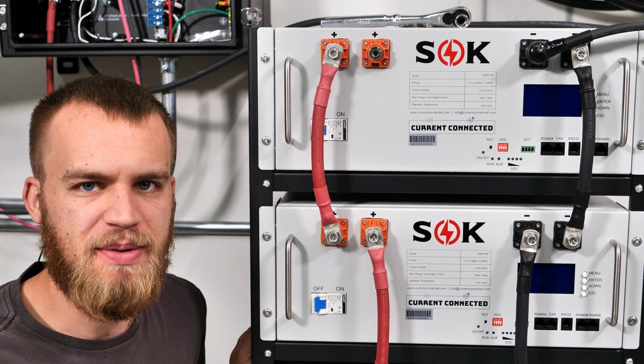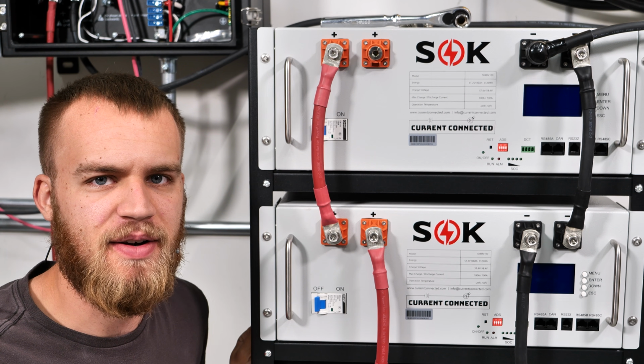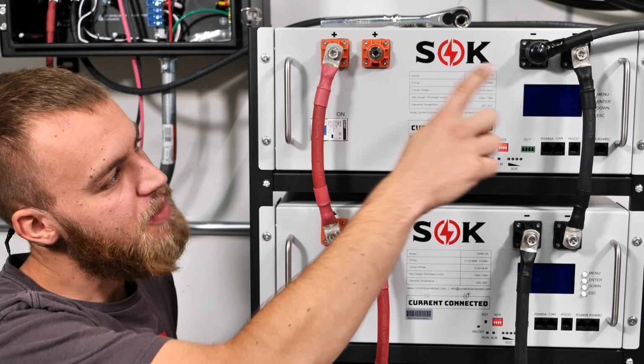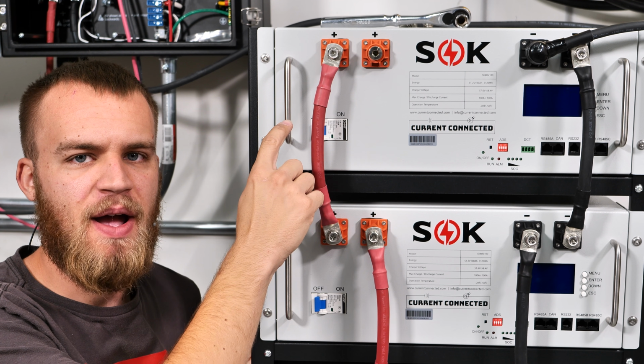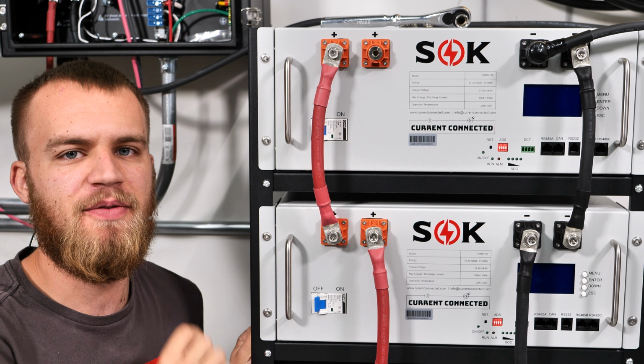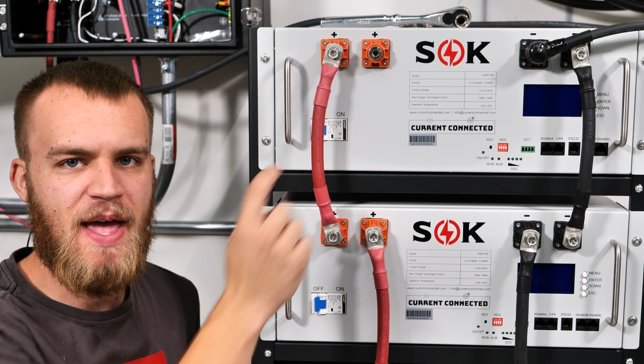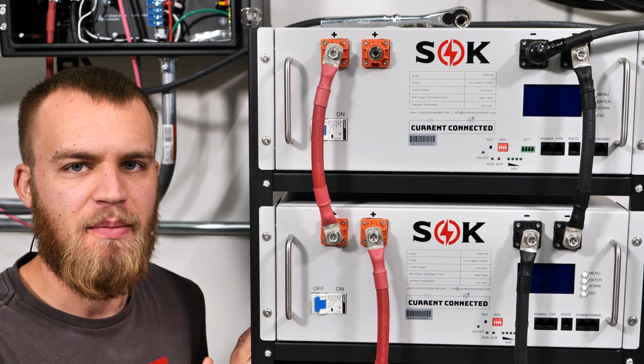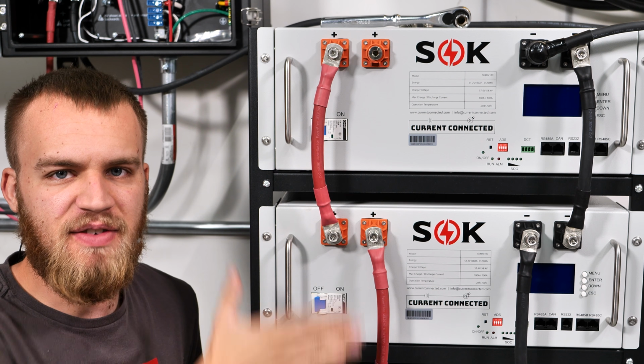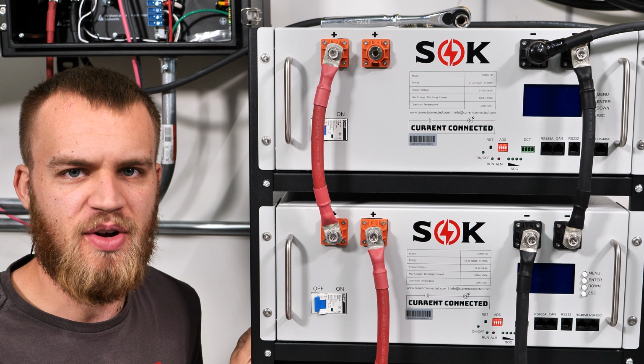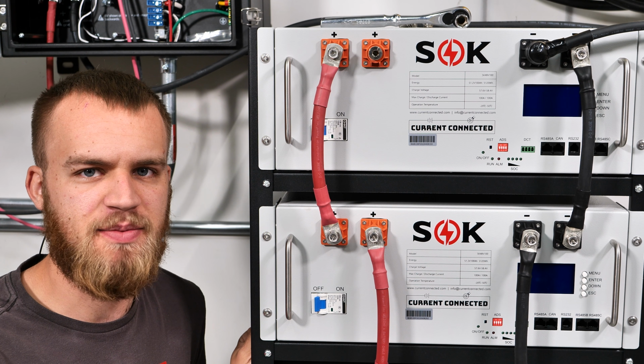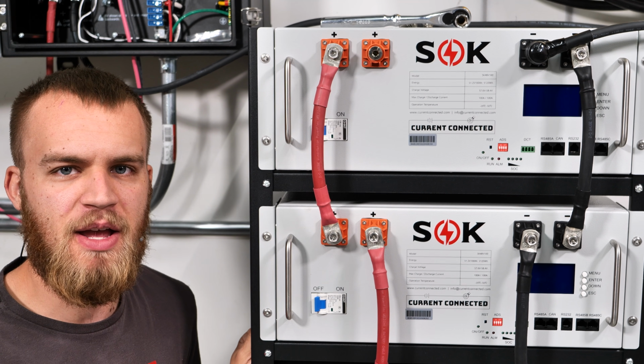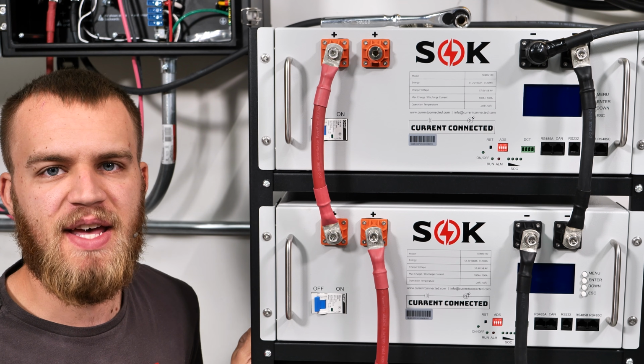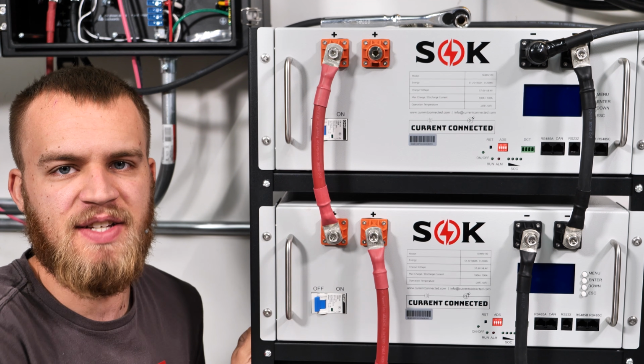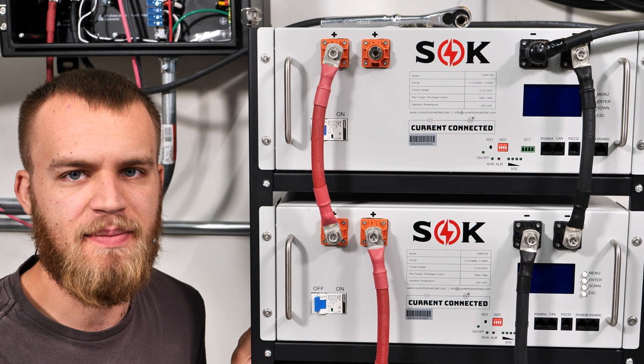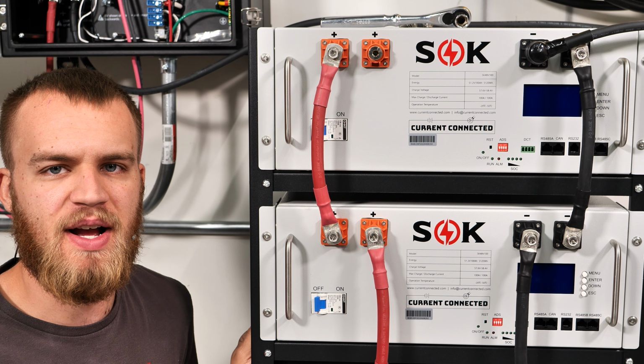Now, why would you put them on opposite corners instead of just the top battery? Well, it's pretty simple. If we connected both cables here on the top battery, then the top battery would be the battery with the least amount of resistance, so more current would come from that battery than the rest of the stack. By going in opposite corners, we're split evenly across all of the batteries, and they'll draw consistently. Additionally, if we hit these batteries with a heavy load, the top battery may be drawn from with too much current, and that can cause it to shut down, leading to a cascade shutdown as you go down the rack. So always connect to opposite corners of the rack like we did here.